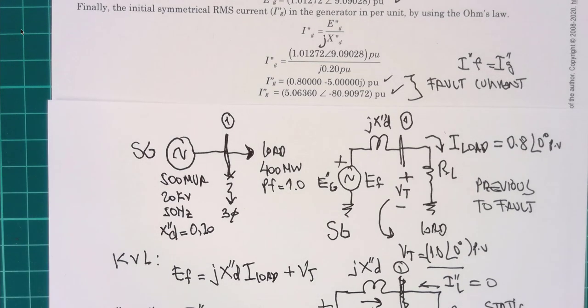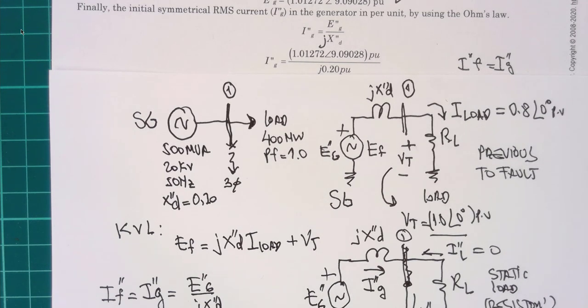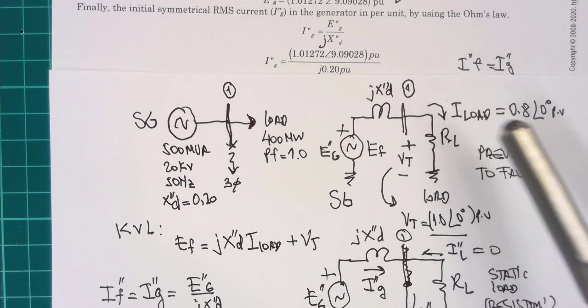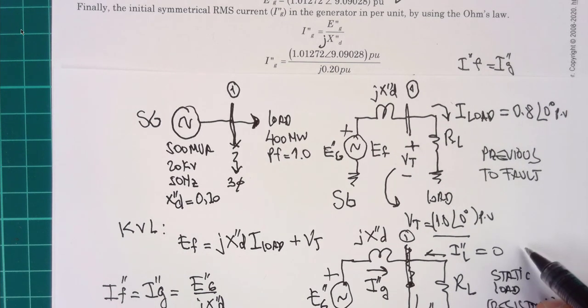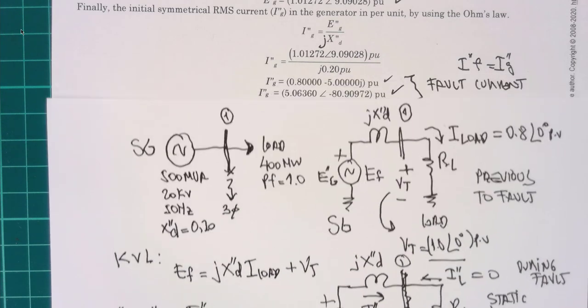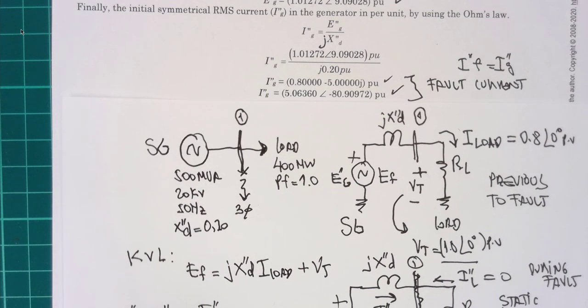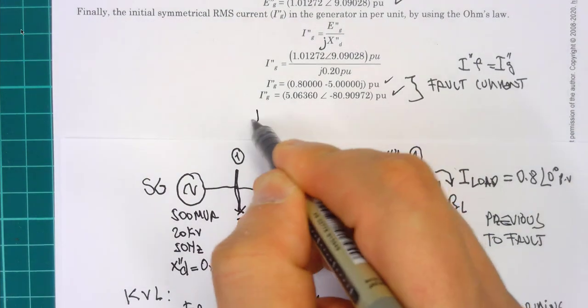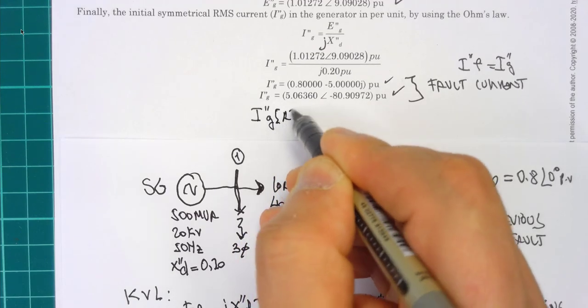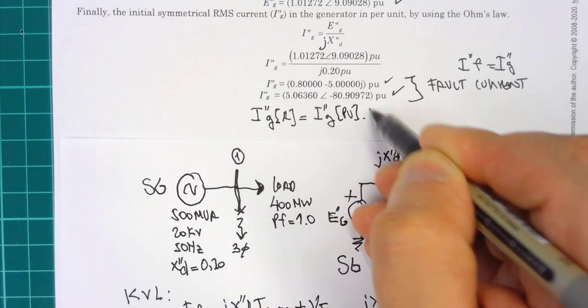This is a straightforward example calculating the short circuit current at the terminal of a synchronous machine using the EMF method. The EMF method requires the pre-fault condition and the during-fault condition. Using basic circuit analysis, we can obtain the short circuit current in per unit. You can also calculate it in amps by multiplying the per-unit value by the base current.